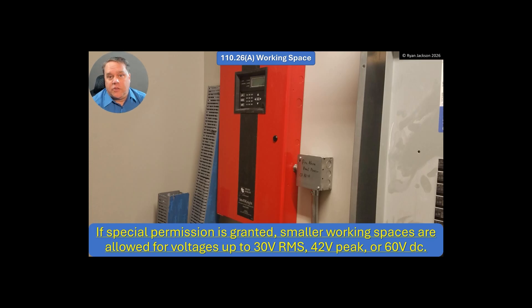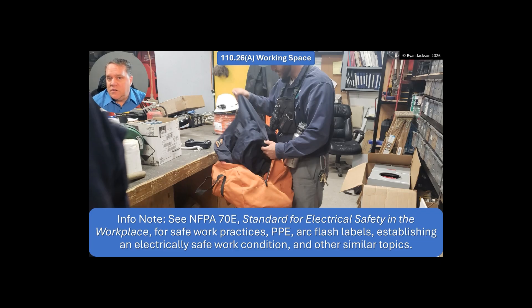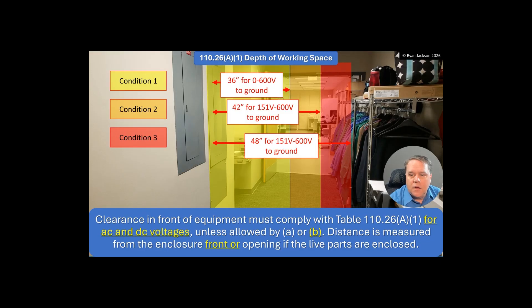There's still an informational note here that says to reference NFPA 70E — Standard for Electrical Safety in the Workplace — for safe work practices, PPE, arc flash labels, establishing an electrically safe work condition, and similar topics. 110.26(a) is for working energized, and NFPA 70E tells you how to work energized safely: how to dress, lock-out/tag-out, how to verify absence of voltage.